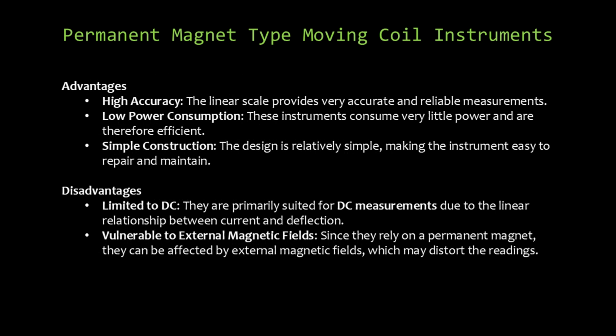Like any sophisticated measurement tool, permanent magnet-type instruments balance remarkable strengths with inherent limitations. Their advantages include exceptional accuracy, incredibly low power consumption, and a wonderfully simple construction that enhances reliability. However, they're primarily limited to DC measurements and can be vulnerable to external magnetic field interference. This vulnerability means they require careful handling and controlled environments. Understanding these characteristics helps engineers and researchers select the most appropriate measurement tool, balancing the instrument's incredible precision against its specific operational constraints.